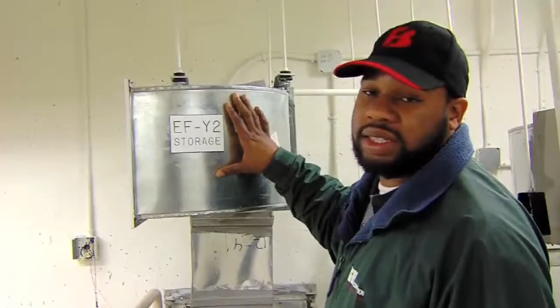For starters, inside the storage room, we have an exhaust fan, which is right here, the EFY2. This exhaust fan is set to 90 degrees, and whenever the ambient air temperature inside this room reaches 90 degrees or above, the exhaust fan will have a close contact to come on, and it will exhaust air out into the atmosphere. It's a pretty simple operation, and that's how this works.